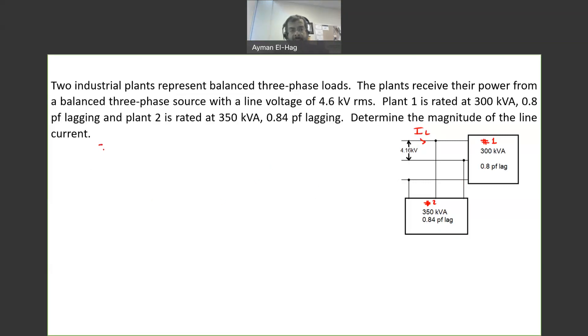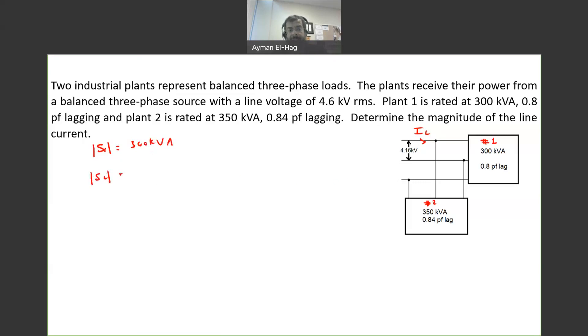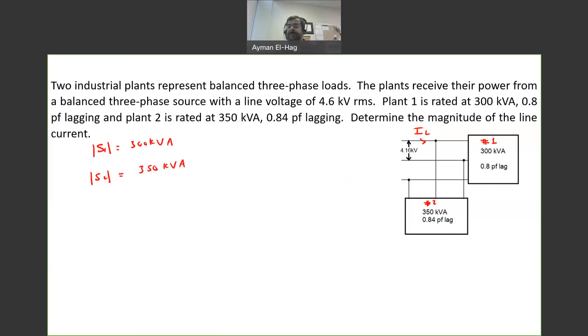S1, the apparent power of load one, is equal to 300 kVA. S2 for load number two is equal to 350 kVA. However, I cannot simply add S1 plus S2, because this is just the magnitude of a vector.